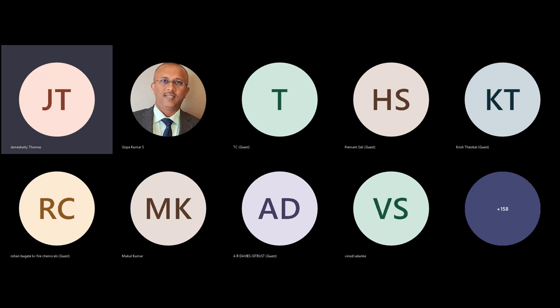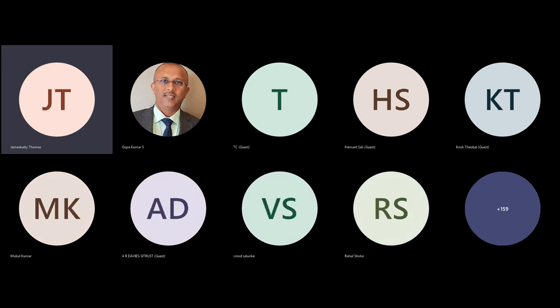Throughout our regulation, or as per the rules in India, there is no such authority as the sanctioning authority of lightning protection. But the electrical inspector is giving permission for lightning protection in multi-storied buildings as per regulation 36, or in the new draft, regulation 38. So I am suggesting that in the new draft, you add lightning protection as compulsory in regulation 38.